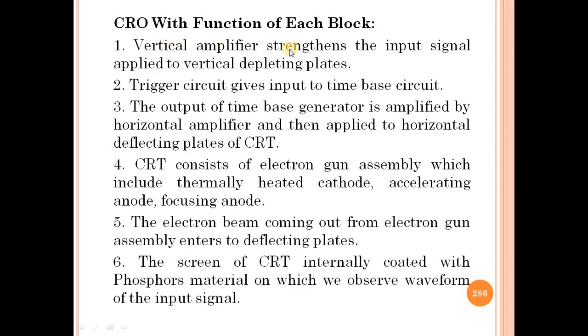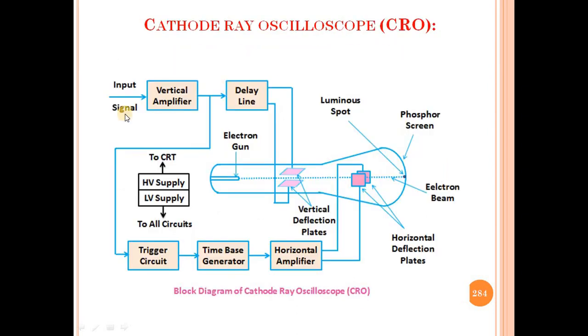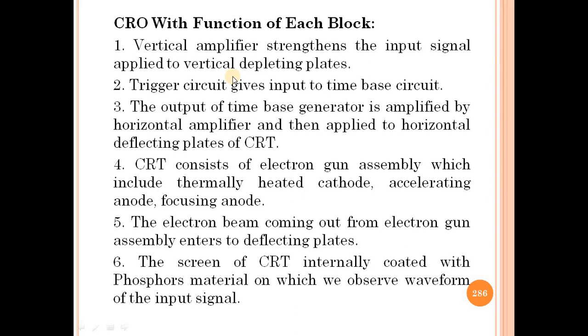The first block is the vertical amplifier. The vertical amplifier strengthens the input signal applied to the vertical deflecting plates. So the input signal is amplified by the vertical amplifier and then sent to the vertical deflecting plates.